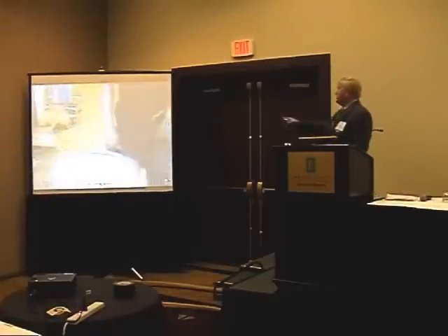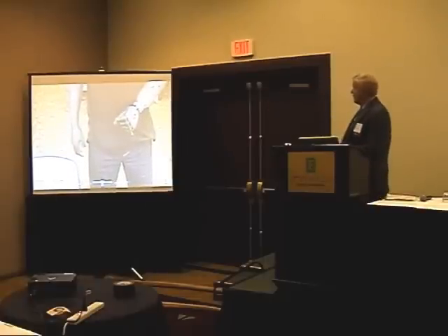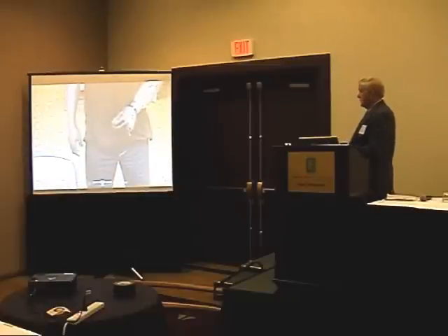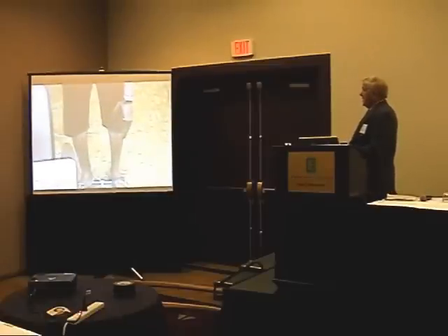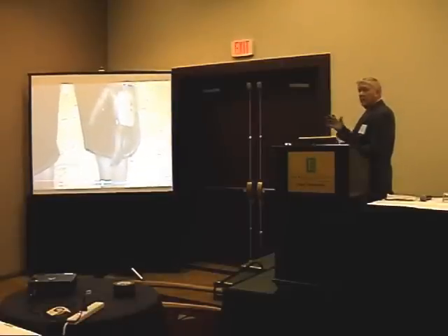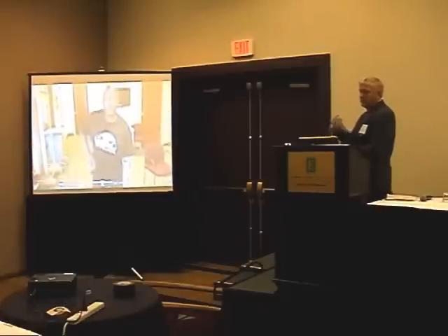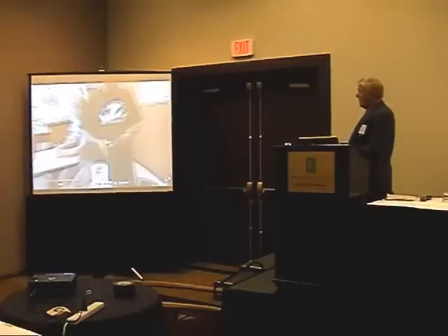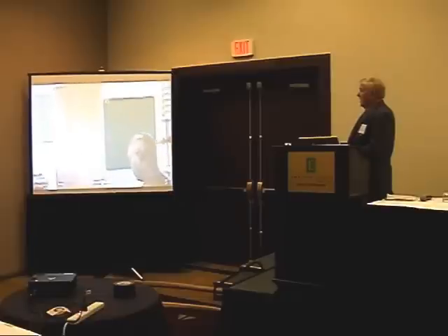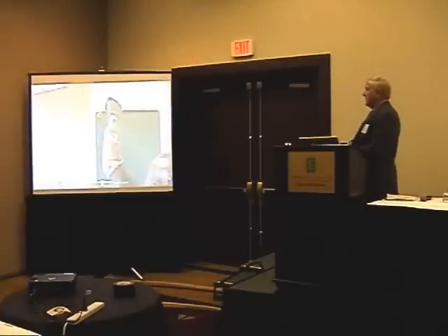Self-suspending socket. What you'll notice on the outside of the arm are the attachment points for the cable control. We use the Otto Bock threaded adapter in order to put a Grip 3, the TRS Grip 3, on that, so he can pop that thing in and out of there really quite quickly. He also has one for doing push-ups. It looks like a fist. For those of you who haven't seen the dexterity on these multi-articulating hands, he's a good example to demonstrate that.